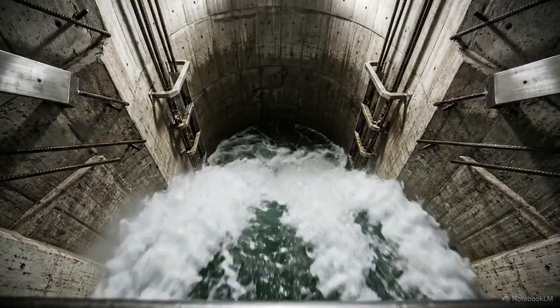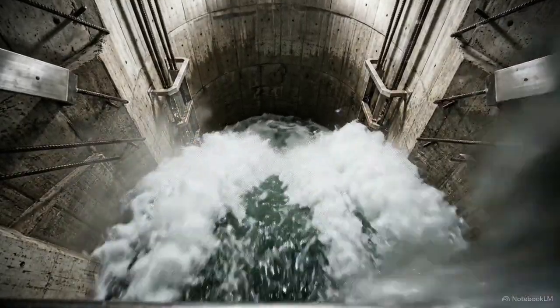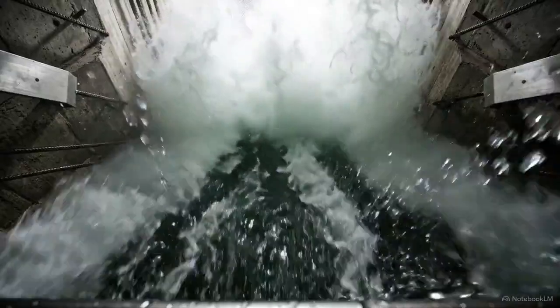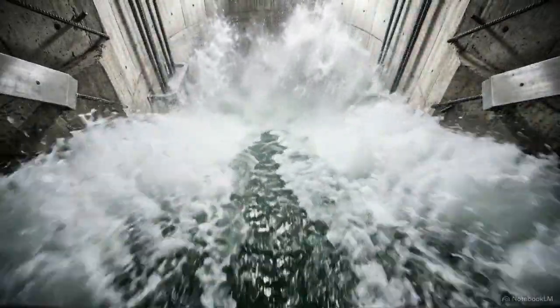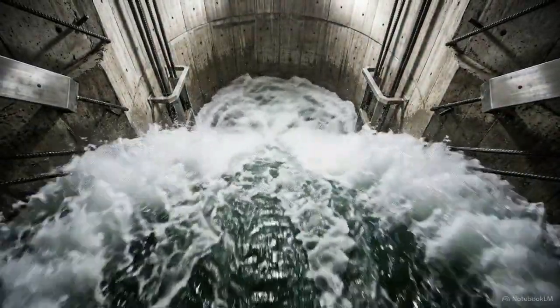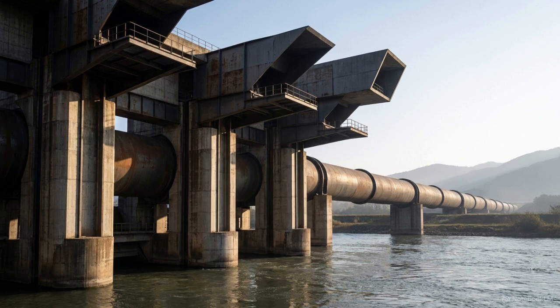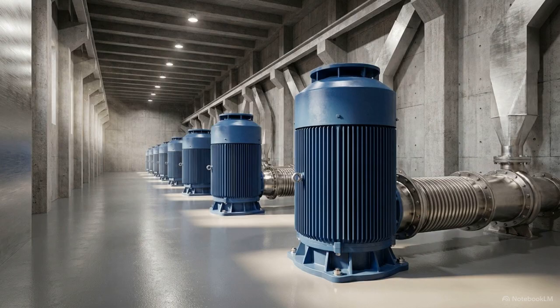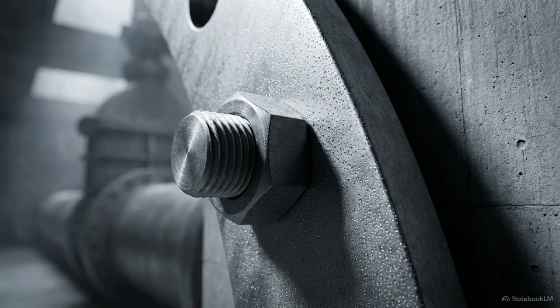To push 20 million liters of raw water through an 18-kilometer pipeline every single day requires an immense continuous injection of energy. Achieving that target flow rate forces the plant to pump against a massive 202.5-meter static head. The mechanical solution relies on a bank of 650-kilowatt vertical flange-mounted motors spinning at 1480 RPM to drive the turbines. But generating this much force introduces a severe physical threat.